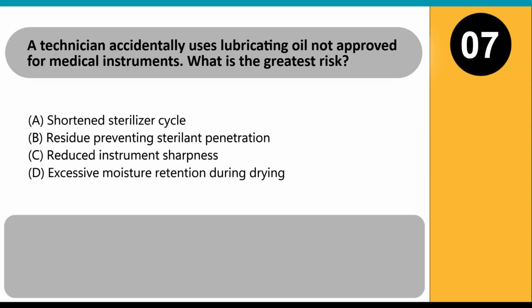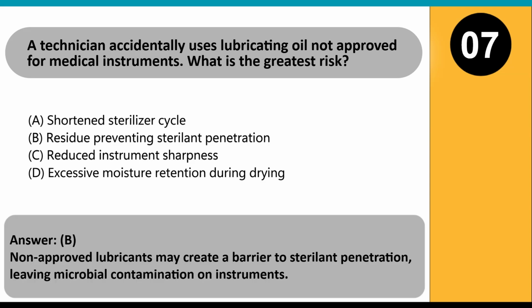outbreaks. A technician accidentally uses lubricating oil not approved for medical instruments. What is the greatest risk? A. Shortened sterilizer cycle. B. Residue preventing sterilant penetration. C. Reduced instrument sharpness. D. Excessive moisture retention during drying. Answer: B. Non-approved lubricants may create a barrier to sterilant penetration, leaving microbial contamination on instruments.